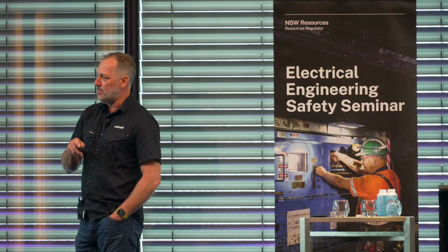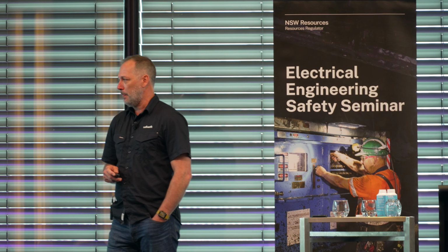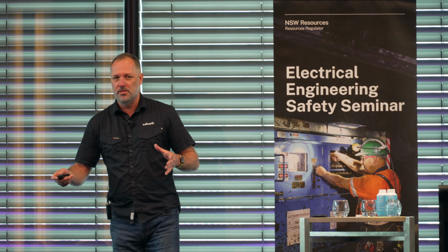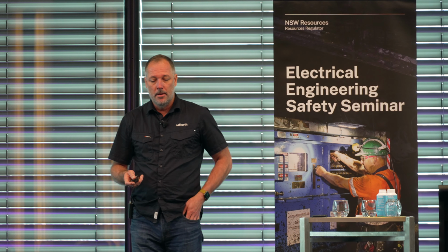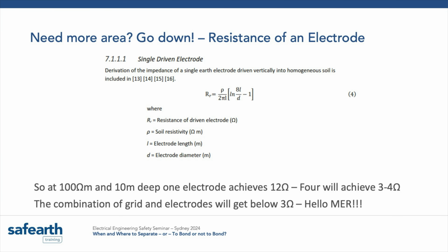I should have probably said 5, but you can really knuckle down onto a number pretty quickly with that simple solid plate equation formula. And so you imagine you've got a bunded transformer sitting there and you've put an earth ring around it and it all measured up to about 10 metres by 10 metres. That's a very, very handy formula. If you need more area, you can go down. And earth electrodes are a pretty obvious thing, but they increase the effective area of your earth grid by going down. And the formula there, these formulas are out of IEEE 80. You'll find them in our ENA EG1 document.